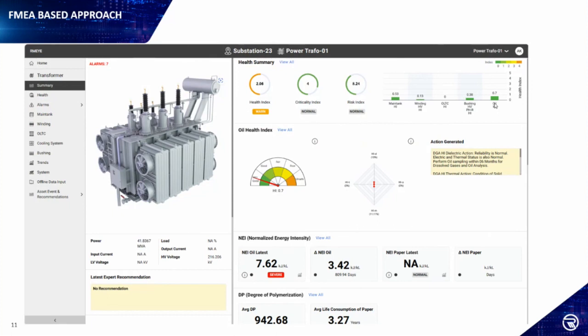Every piece of information related to condition monitoring is very crucial. I'll give you an example of maintenance or repair. If oil regeneration has been done on the transformer, and we just rely on the oil health index based on different gas compositions and oil quality data, then after regeneration the oil health index becomes really good.